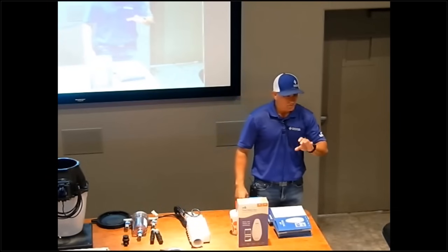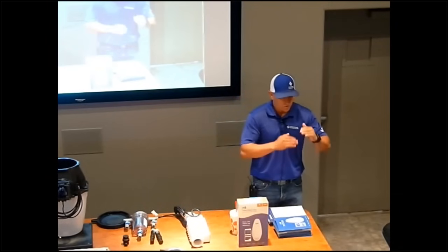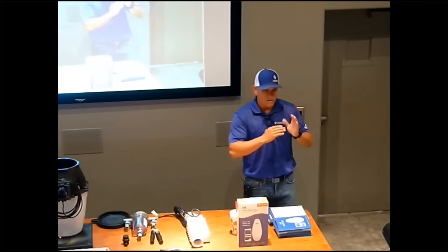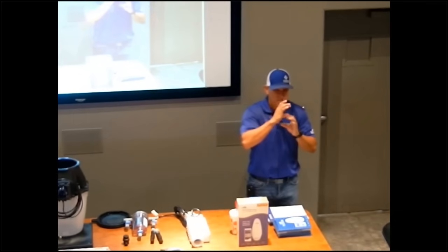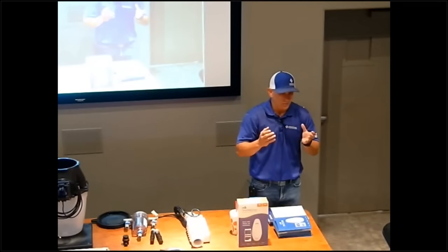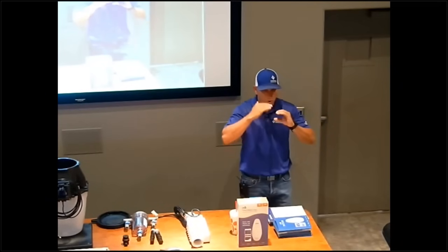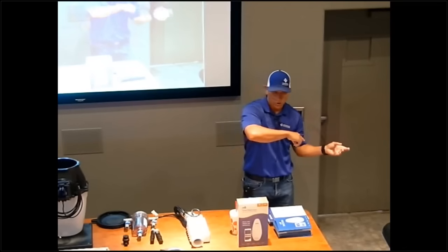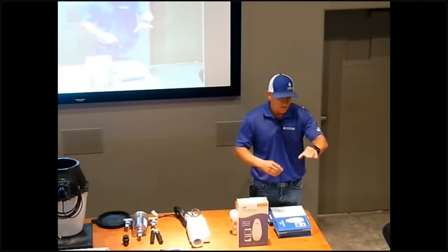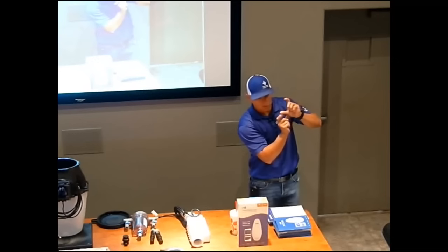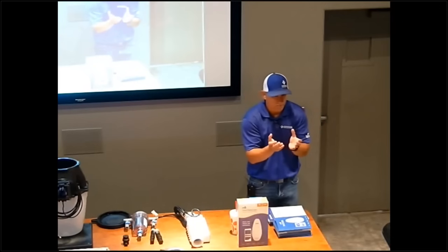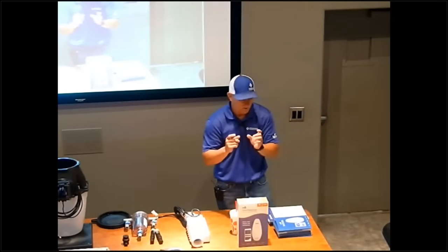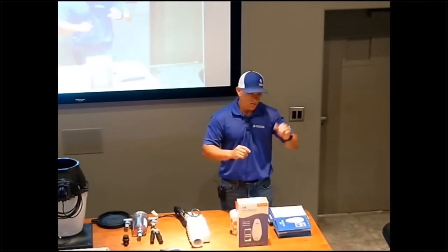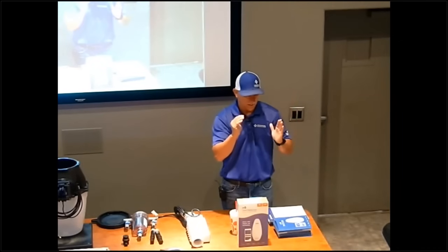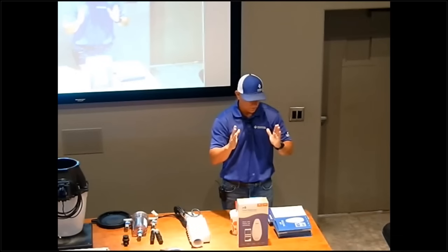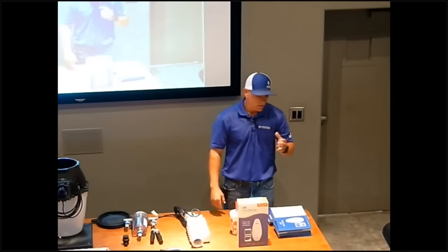As long as you have it set right, you don't actually need to stagger them. If you have both set to start at 12 and your high speed kicks in, the high speed will just override — it doesn't matter, because any higher RPM overrides the lower RPM. So as long as they start at the same time, it's totally okay, but you don't need to do that. You could use low then high, but if you have 12 to 8 high and 12 to 4 low, for example, that's totally fine too.